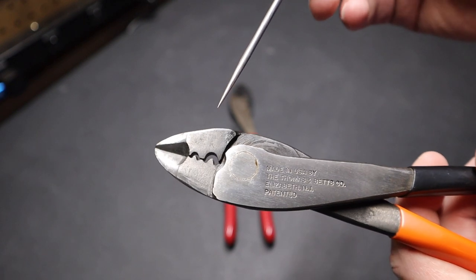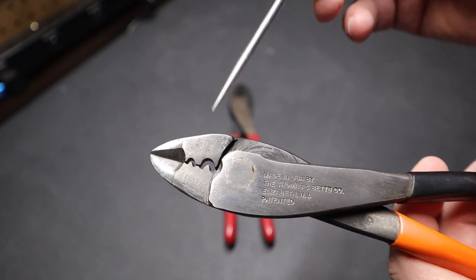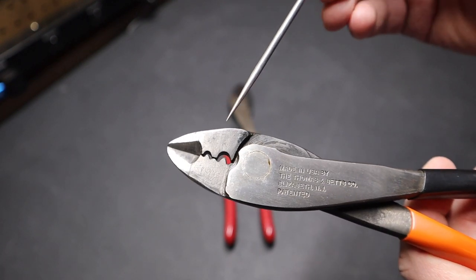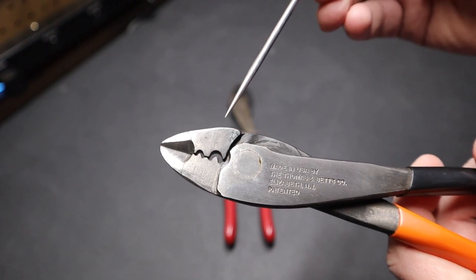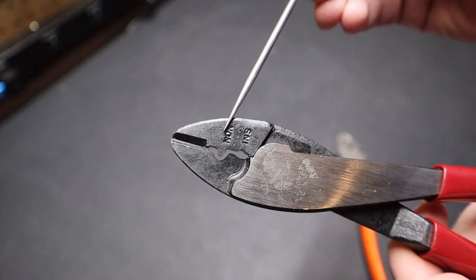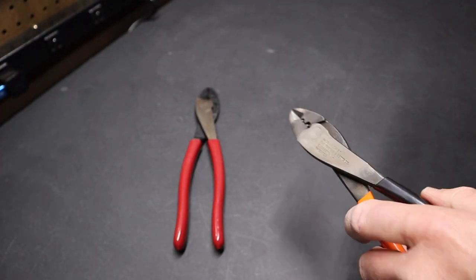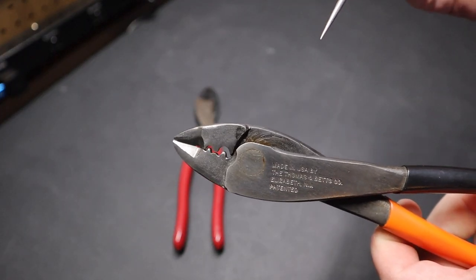And time after time, I've seen people who, regardless of whether they're crimping insulated or non-insulated, they always use the non-insulated part of the die. So people who use this Klein tool I've seen repeatedly, they just go for everything they're doing. They do the non-insulated part of the crimp tool. They don't even use this part of the tool. That's something I liked right off the bat about this Thomas and Betts crimper.